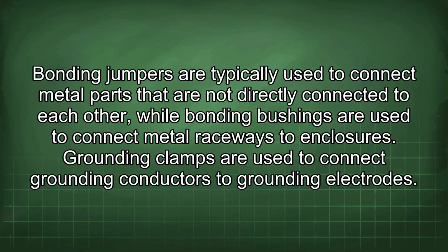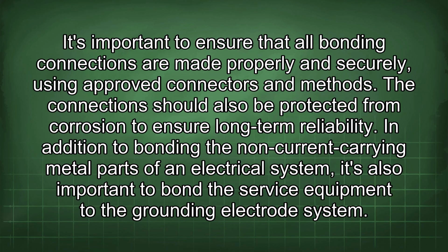Bonding jumpers are typically used to connect metal parts that are not directly connected to each other, while bonding bushings are used to connect metal raceways to enclosures. Grounding clamps are used to connect grounding conductors to grounding electrodes. It's important to ensure that all bonding connections are made properly and securely, using approved connectors and methods. The connections should also be protected from corrosion to ensure long-term reliability.